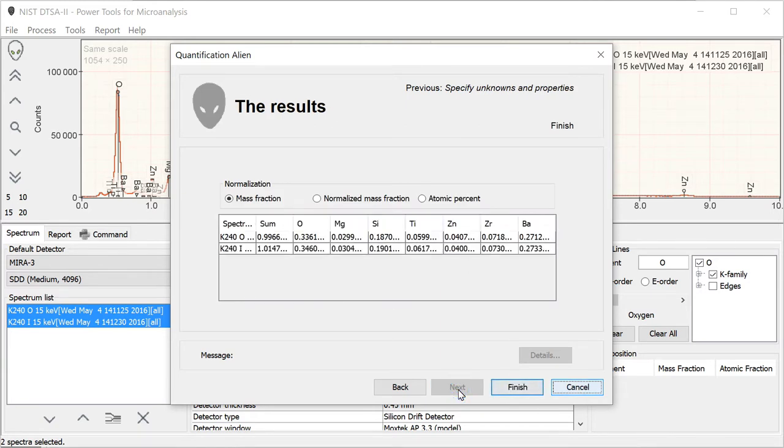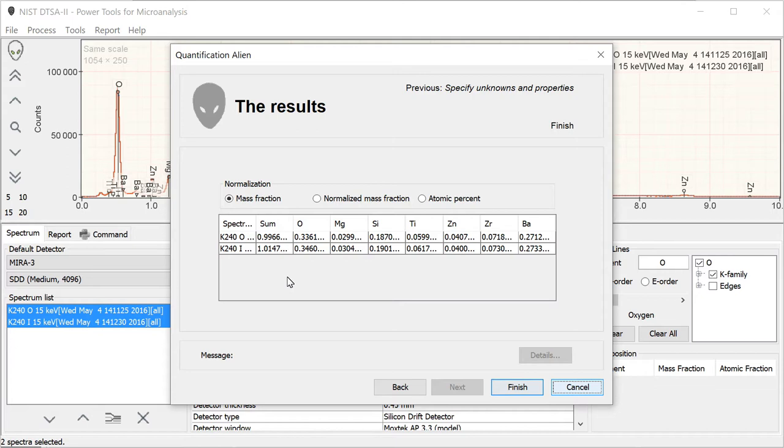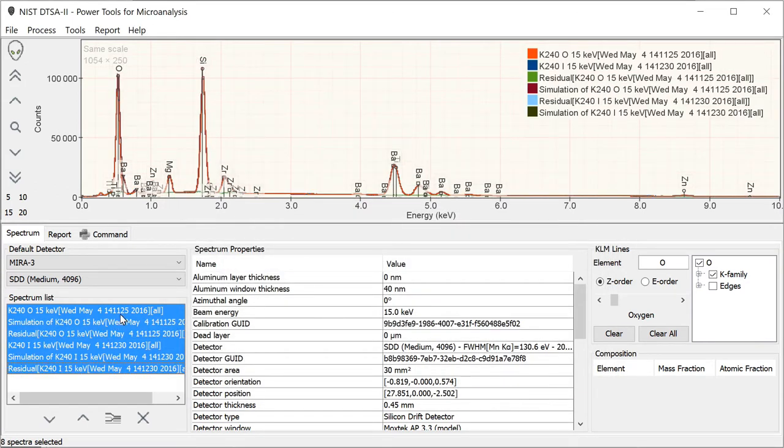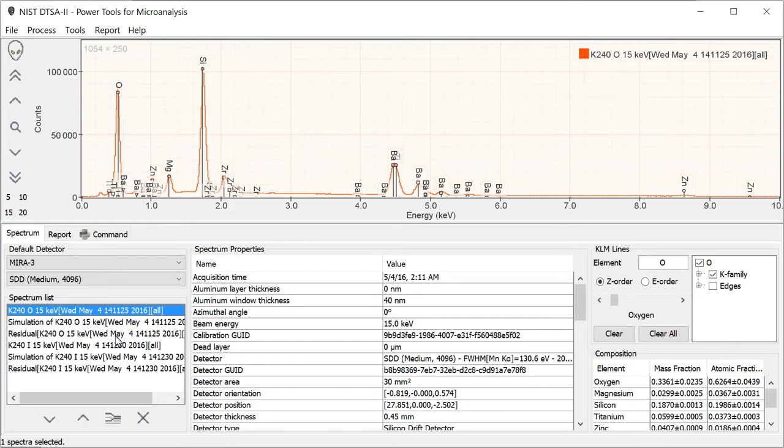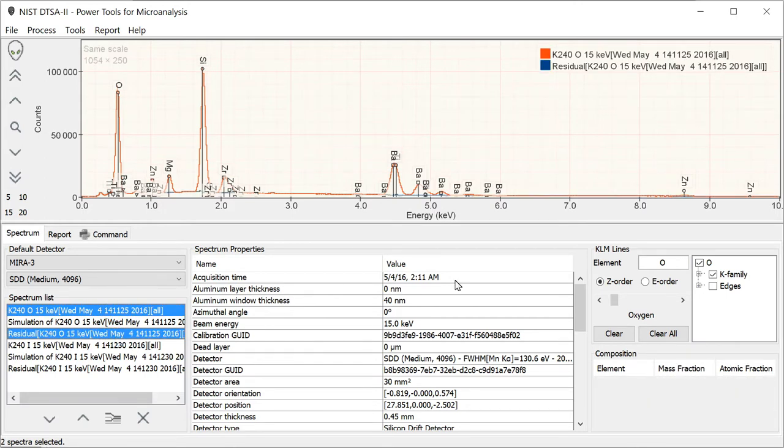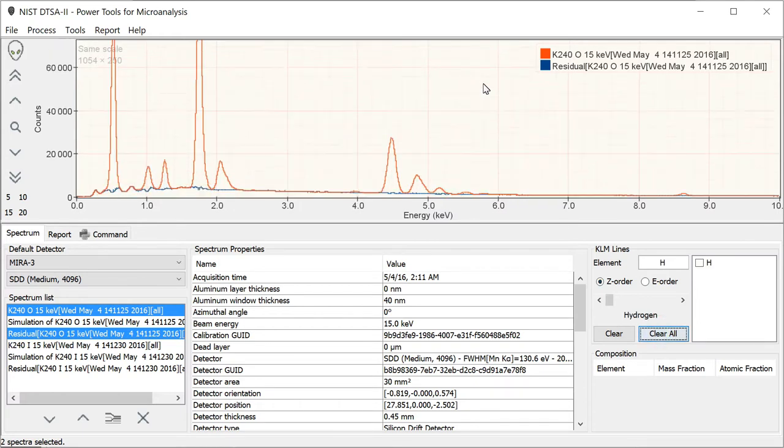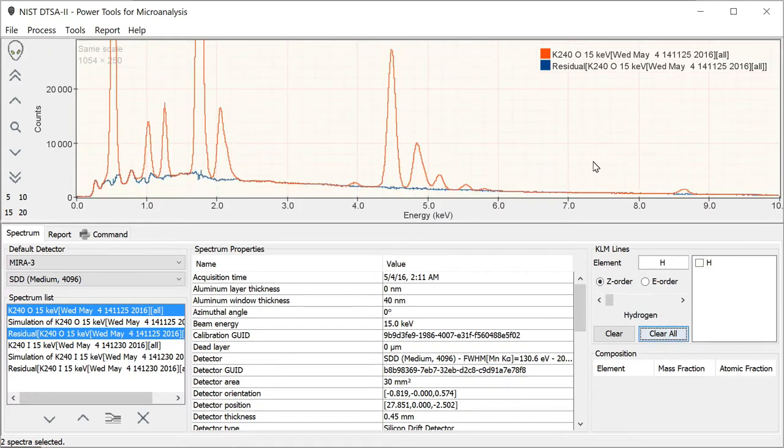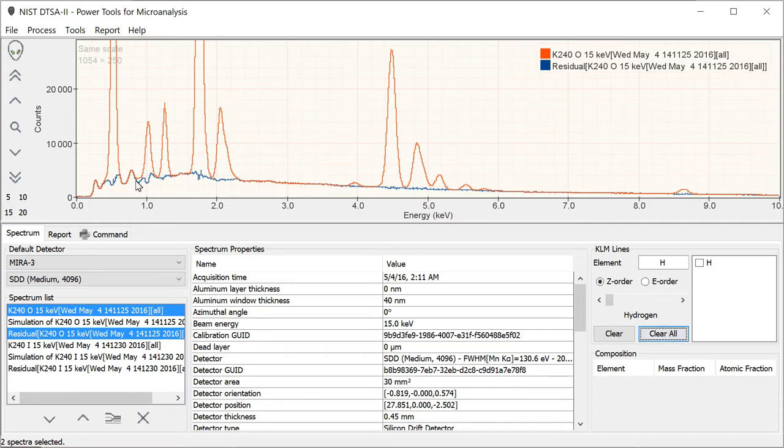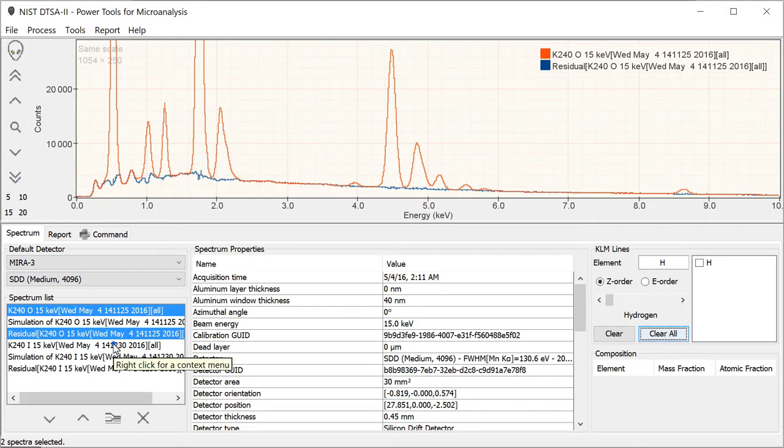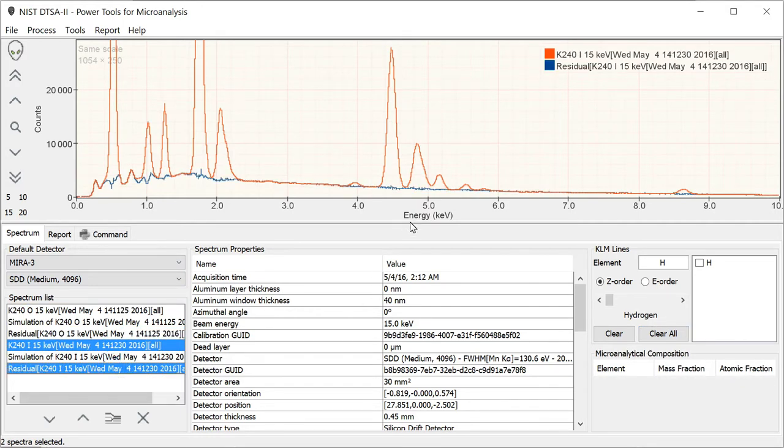My first thing is I look at the analytical total, the sum, and those look reasonable, within plus or minus a percent or two of unity. My initial inclination is that the quant went reasonably well. My second check is to look at the residual. I'm actually going to clear all the lines because they kind of confound things. If we look at the residual, we can see that it looks pretty clean in here. There is one line in here that we've kind of missed, and that is this barium M line. That's because in this particular instance, we're not using the M lines. We're sort of ignoring the M lines of barium in this quant. So that peak would be removed if we were looking at that. For the other one, similarly, good-looking residual. So that suggests things went well.